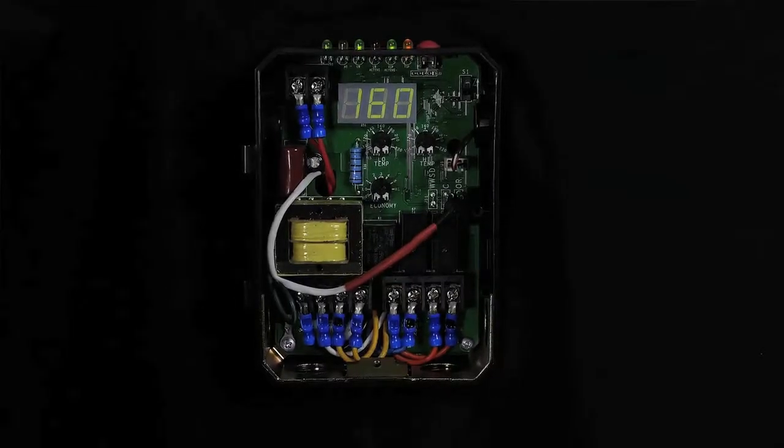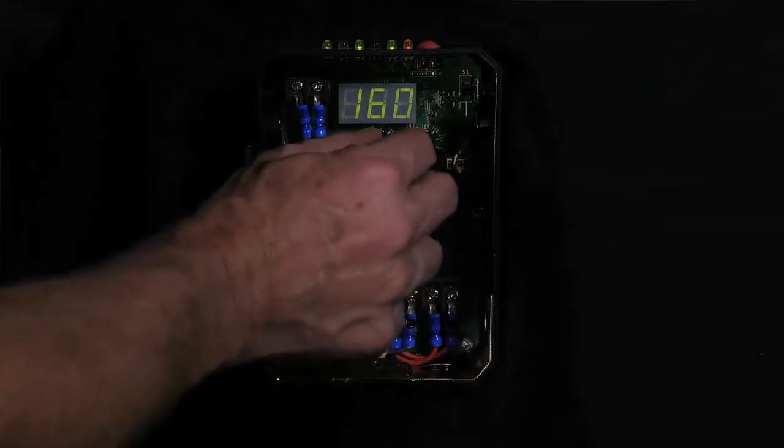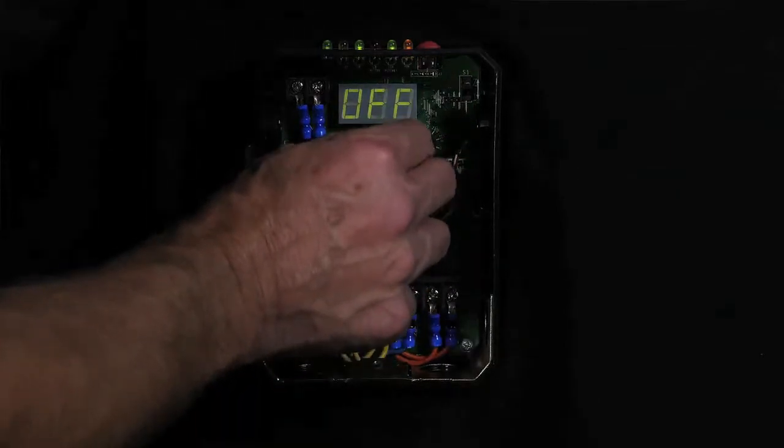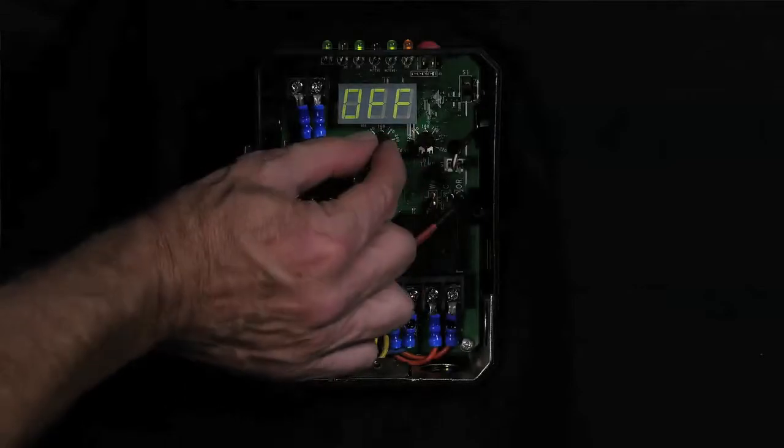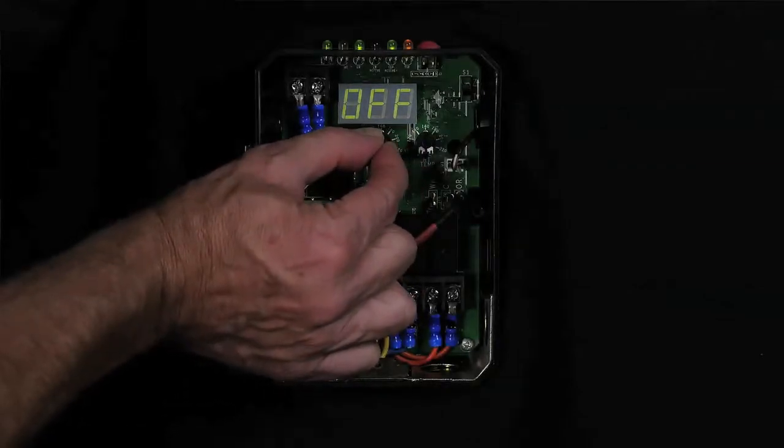To access these features, you must enter the program mode. Start by turning the low temp dial fully counterclockwise until the display reads off. Now slowly turn the dial clockwise until you see PRO on the screen. You are now in the program mode.